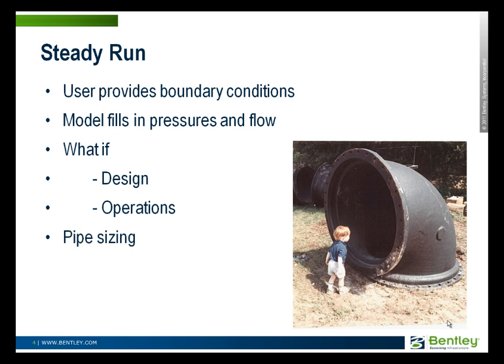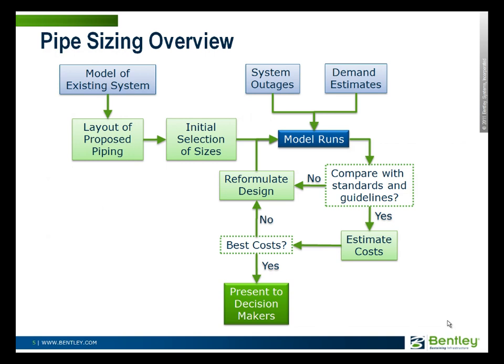The most basic of those is pipe sizing. This is a fundamental reason that these distribution models were developed in the beginning — to figure out how big pipes should be. Essentially you start off with the model of your distribution system, lay out the piping that you're proposing to use, and make your initial selection of sizes. You pick some reasonable sizes that you think are going to work, and then you run the model. In addition to running the model for the system as you expect to install it, you'd also be accounting for uncertainty in demand estimates and the potential for outages of individual components.